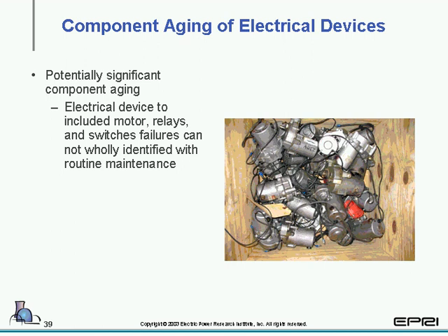And then what we're going to look at is component aging of electrical devices. When we look at these particular pieces of equipment on the breaker, they fail or tend to fail digitally. Just because you test it and it works correctly doesn't mean it's going to continue to work correctly. So if you start to see a trend of failures with any type of electrical device or component, i.e. motor or relay, you might want to consider, before the failure, making those part of the parts kit we just talked about, or having those on hand.